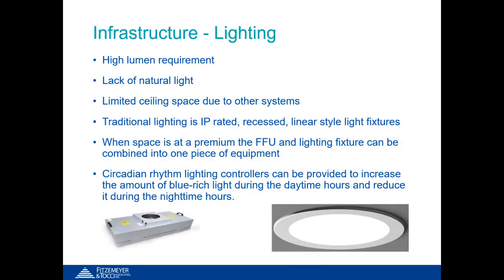The two biggest challenges when it comes to providing lighting within pharmacies are limited ceiling space and lack of natural light. Ceiling space is at a premium within pharmacies, and once all of the HVAC equipment has been accounted for, there isn't much space left for other trades. This requires light fixtures within compounding areas of the pharmacy to occupy the minimum amount of ceiling space while maintaining a high foot candle level of roughly around 100 foot candles at the work surface for precision tasks.